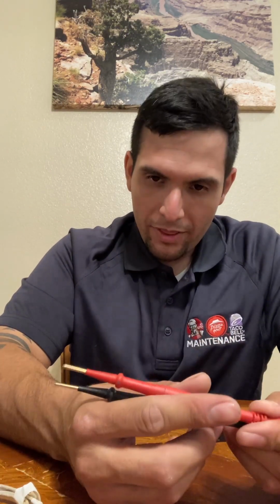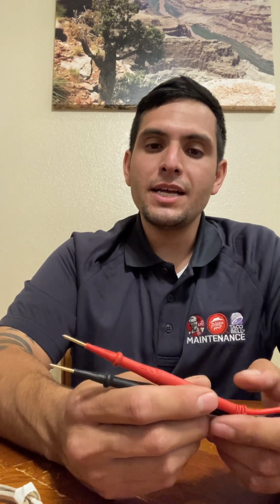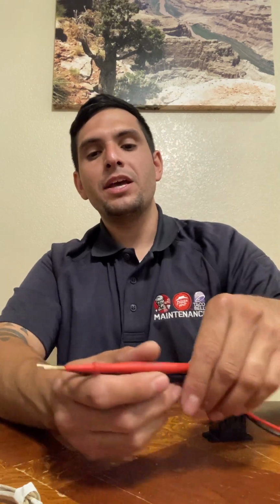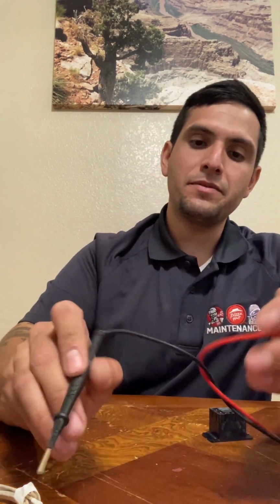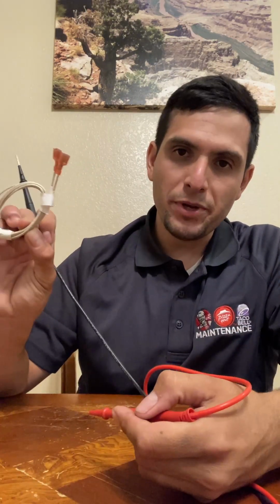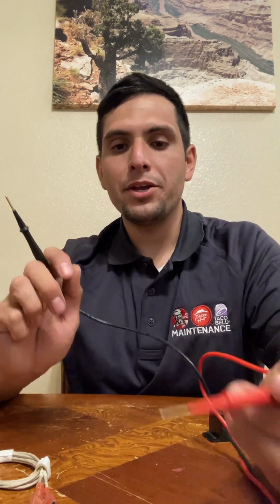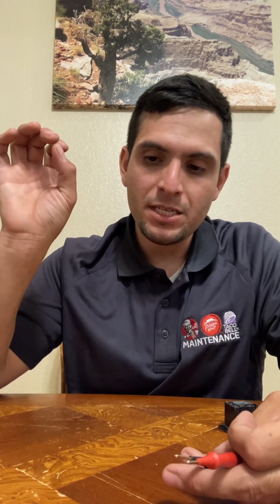You can check the heating elements, you can ohm them out. I don't remember off the top of my head, but you can find in the manufacturer's literature what the proper ohms is for that element, but it's usually not the heating elements. So I tend to check that almost last. And then you've figured out that the probe is doing what it's supposed to, either you ohmed it out, or you know your relay is good, you know your probe's good, but you're still having problems. Sometimes you'll even get some wonky flashing on the screen, or not the normal flashing, but part of the screen disappearing, fading away, or it'll show numbers or symbols you've never seen before.